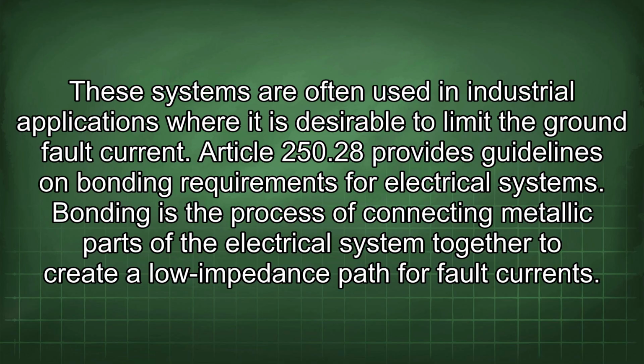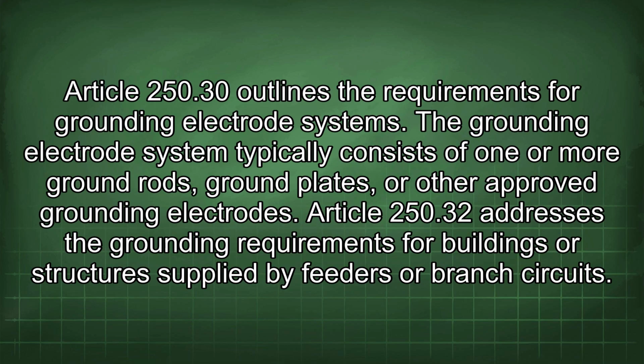Article 250.28 provides guidelines on bonding requirements for electrical systems. Bonding is the process of connecting metallic parts of the electrical system together to create a low-impedance path for fault currents. Article 250.30 outlines the requirements for grounding electrode systems. The grounding electrode system typically consists of one or more ground rods, ground plates, or other approved grounding electrodes.